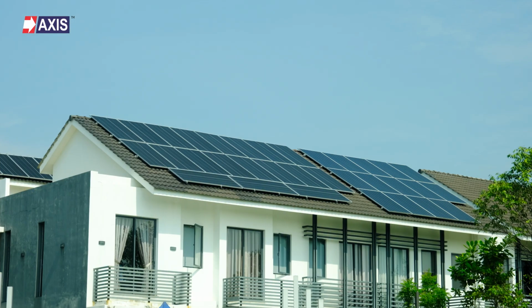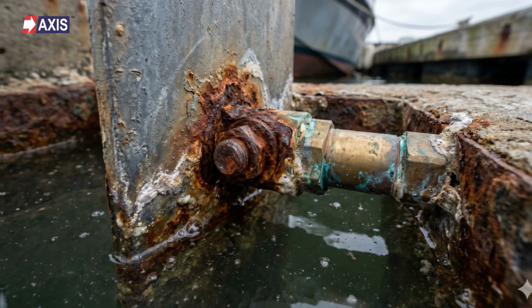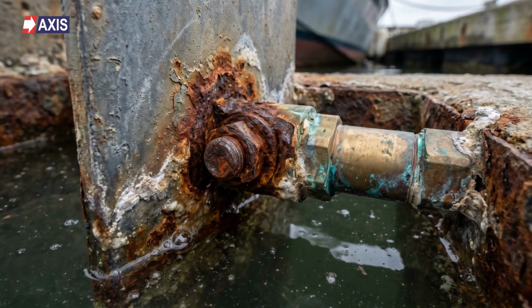But what happens when you pick the wrong one? Let's say you use a dual-rated lug to connect an aluminium cable to a copper bus bar. The tin plating on the lug acts as a barrier between the two metals. As long as that plating is intact, the connection holds. But in outdoor installations like solar plants, rooftops, or coastal areas, the plating is exposed to moisture, salt, humidity, and temperature cycles. Over the years, the plating will wear down, and once it does, aluminum and copper are in direct contact. Galvanic corrosion starts and contact resistance goes up. The joint heats up and the connection degrades.